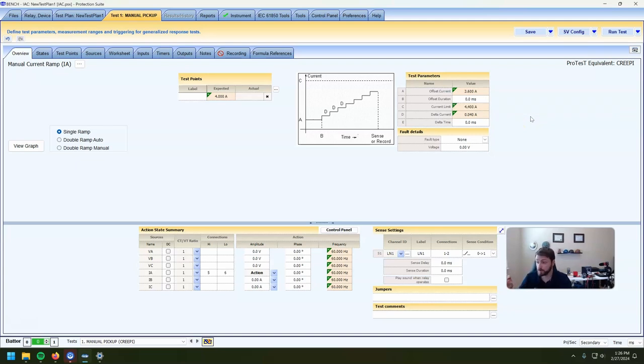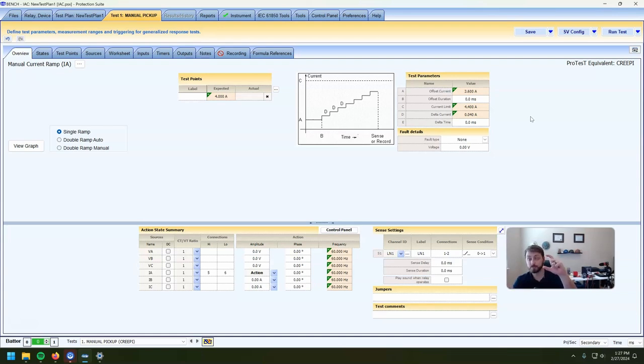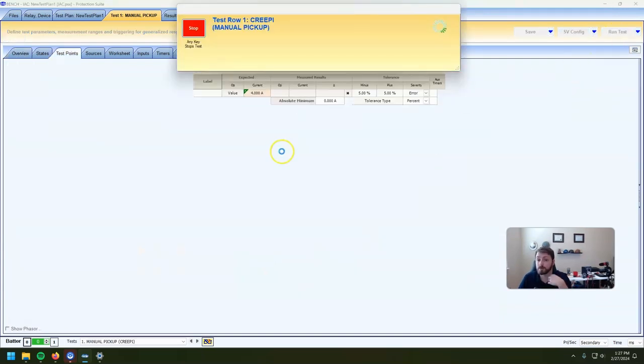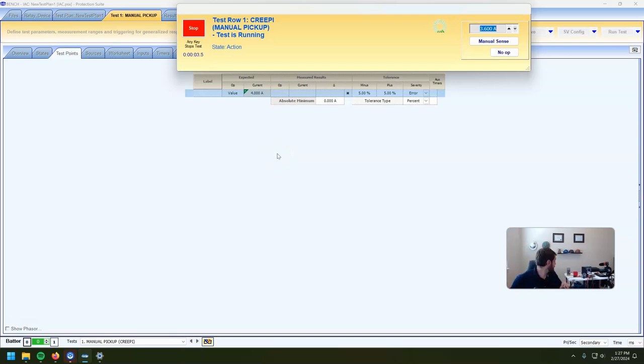One thing to note on this: whenever you're doing any sort of test, we need to start outside our tolerance band and ramp into our tolerance band. My expected result's tolerance is plus minus five percent. So my test is running plus minus ten percent — I'm going to start ten percent below my tap, creep into my pickup zone, and then creep out of it. This is not my recommended way to do this test, but I just want to show you it's totally possible. We can manually ramp this, just bump the current up a little bit until the dial starts to turn.